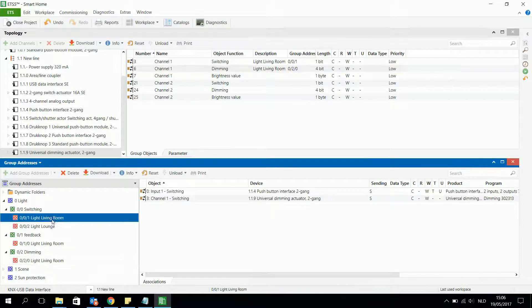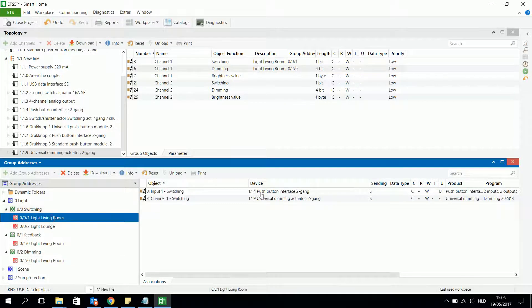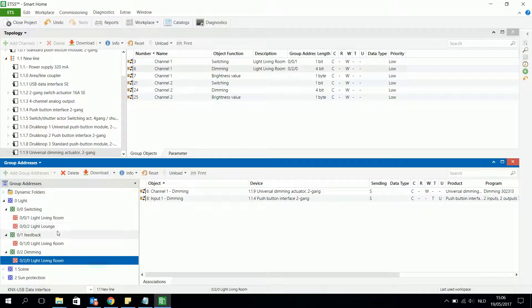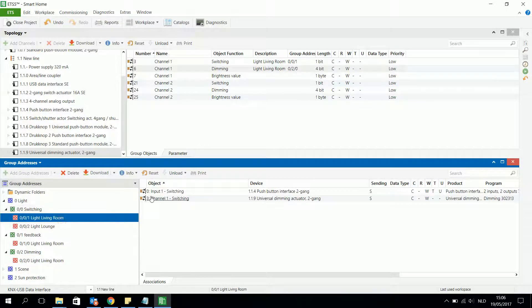As I can see, for the same pushbutton and actuator I have linked the switching objects in one group address, and in another group address I have linked the dimming object of the same pushbutton and actuator. So with one press on the button I can switch it on or off, or make it brighter and darker.